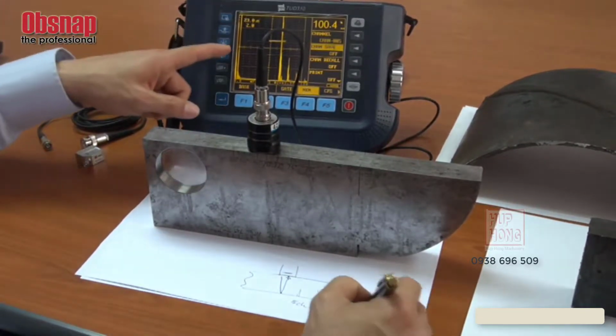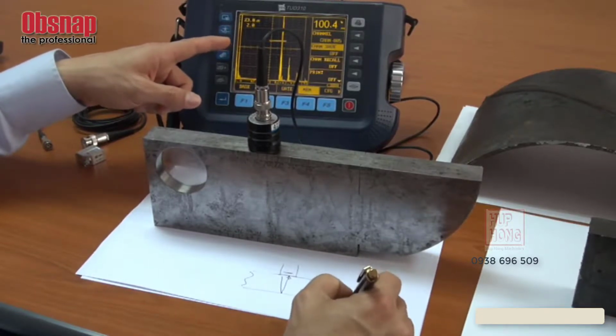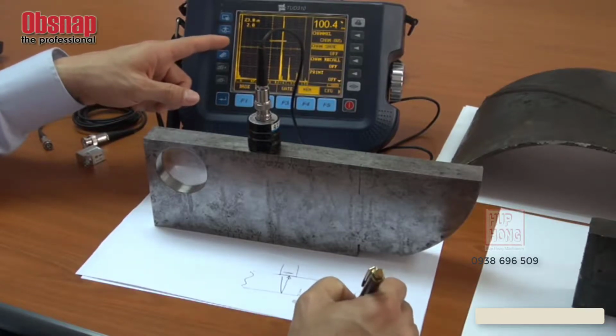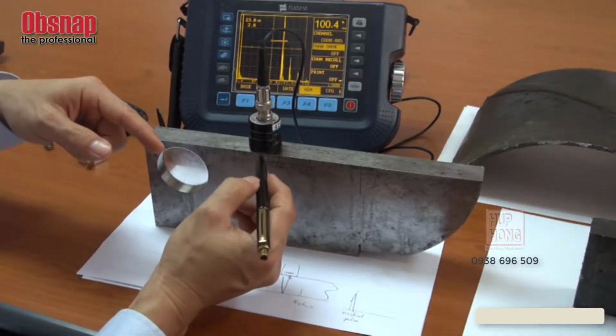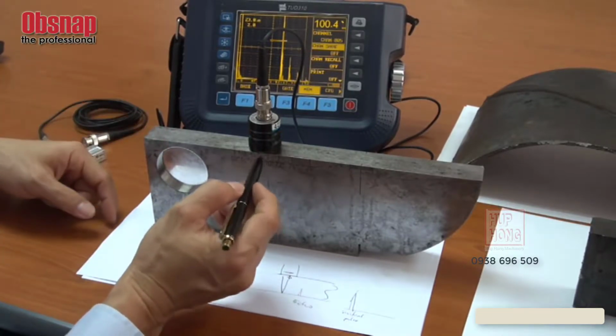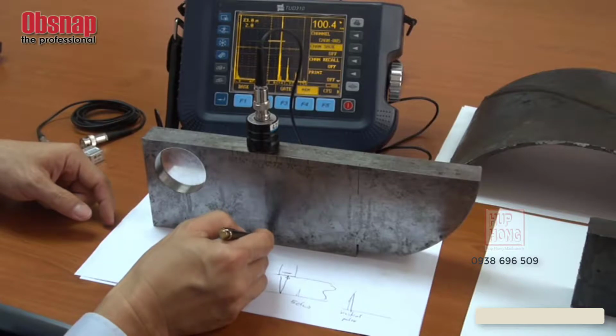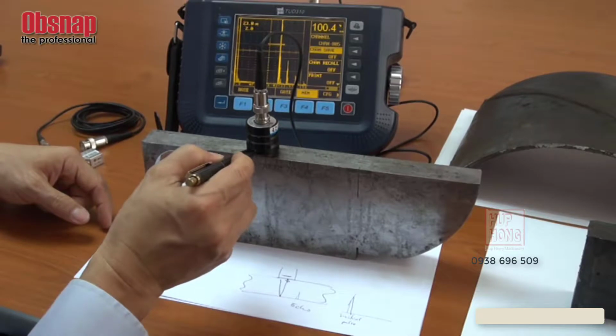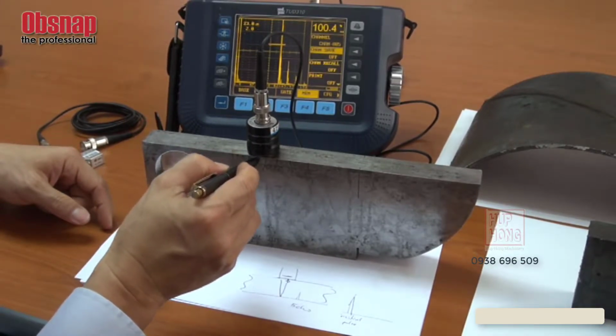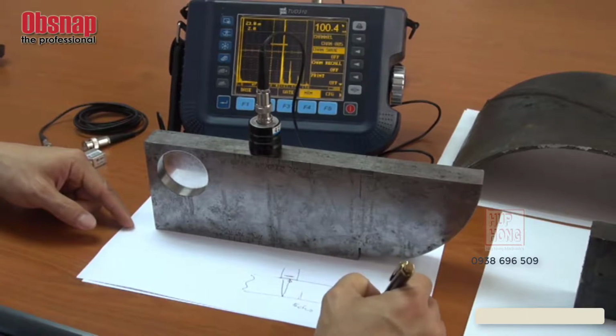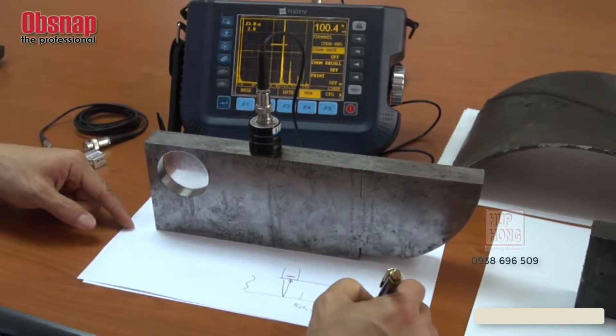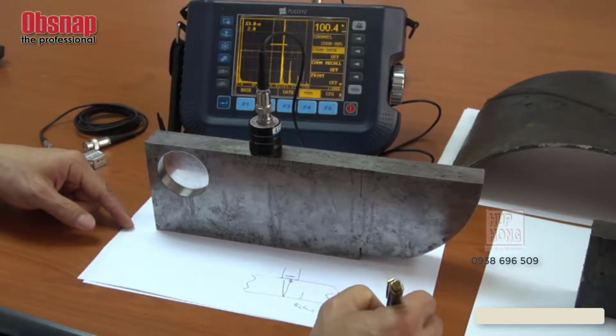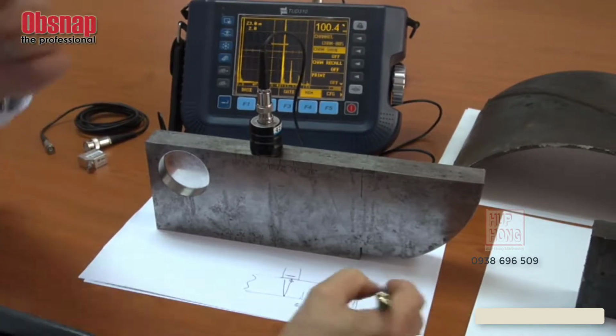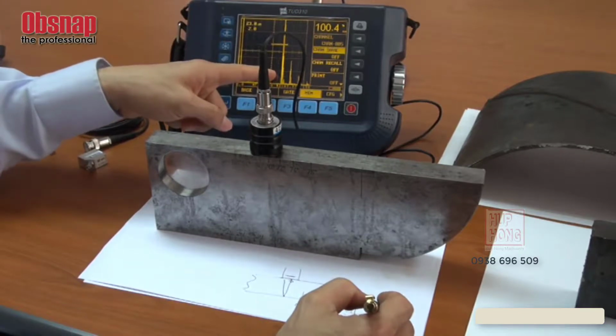Meaning to say that on this screen here, the calibration is first. This is the initial pulse that is sent to the material, right? It comes out from here. Initial pulse comes out from here. Then this pulse transmits in the material. When it hits the back wall of this block, it will be reflected by the back wall and then go back to this crystal. All right, this crystal was sent. Then this is where it sends this pulse. This is called the echo from the back wall. Okay, so this is the echo that we receive.